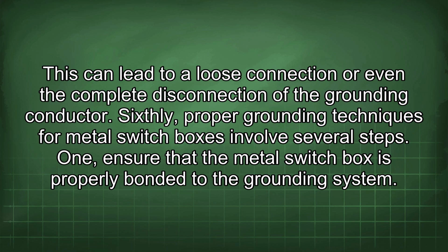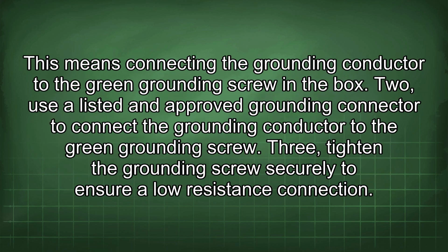Sixthly, proper grounding techniques for metal switch boxes involve several steps. 1. Ensure that the metal switch box is properly bonded to the grounding system. This means connecting the grounding conductor to the green grounding screw in the box. 2. Use a listed and approved grounding connector to connect the grounding conductor to the green grounding screw. 3. Tighten the grounding screw securely to ensure a low resistance connection.